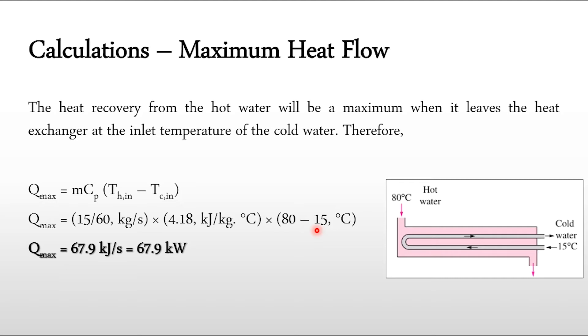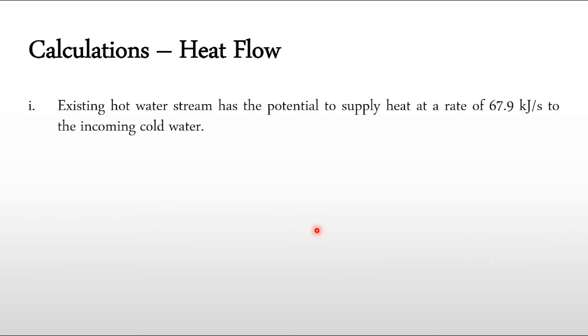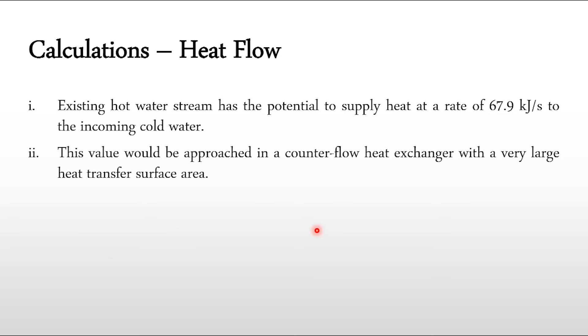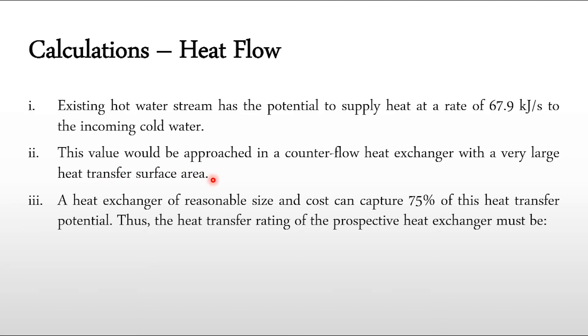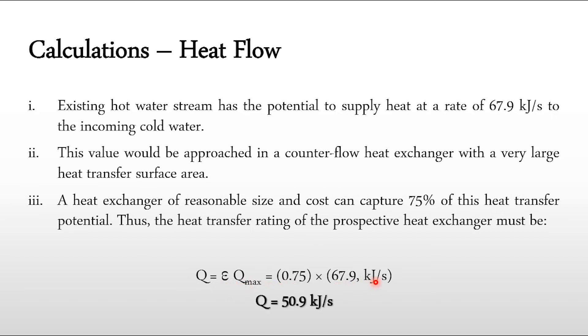The existing hot stream has the potential to supply heat at a rate of 67.9 kW to the incoming cold water, but a very large heat transfer surface area would be required to achieve this. Therefore, we extract 75% of it: Q = effectiveness × Q_max = 0.75 × 67.9 = 50.9 kJ/s. This is a reasonable target — we need to extract 50.9 kW from the drain water to supply to the incoming cold water.